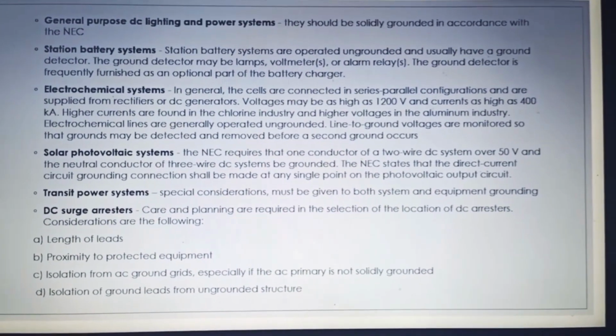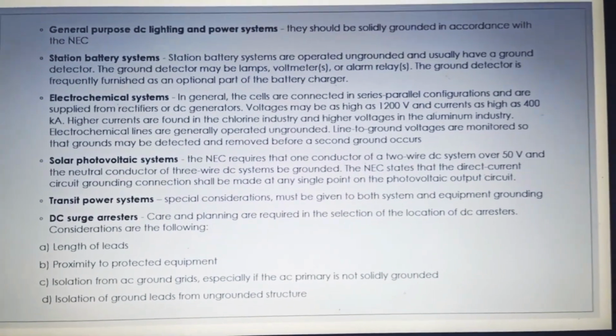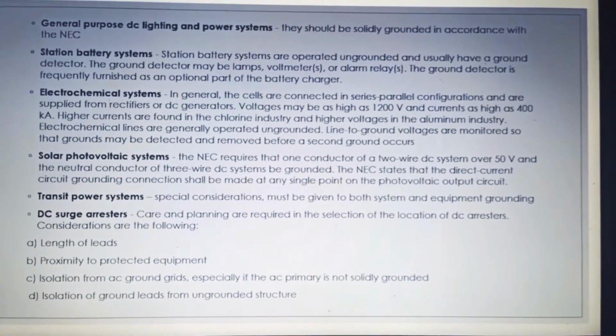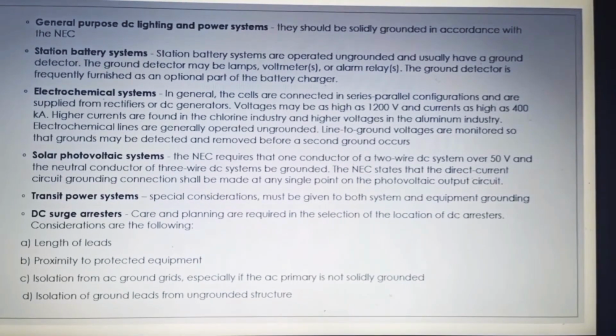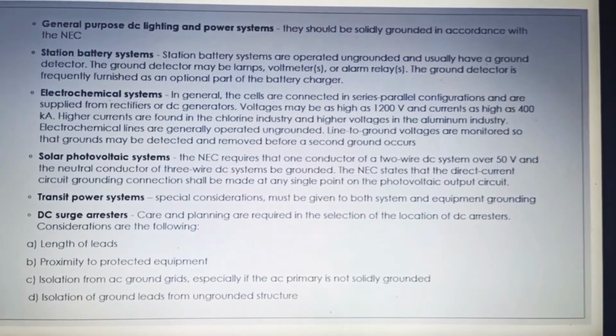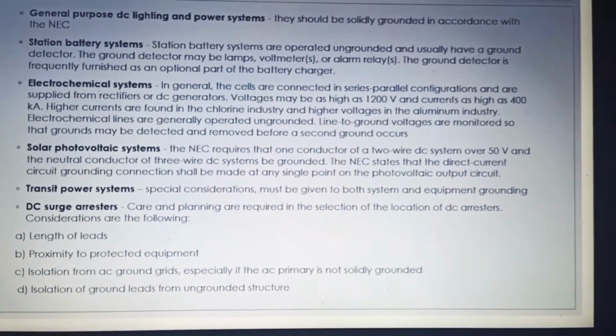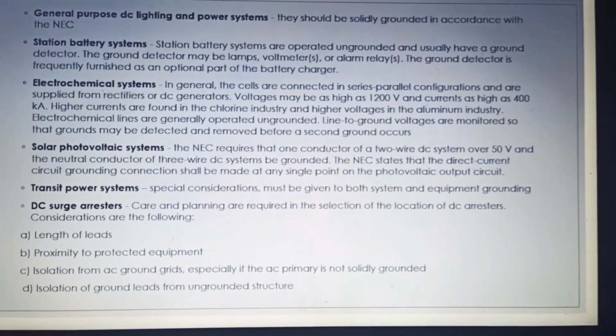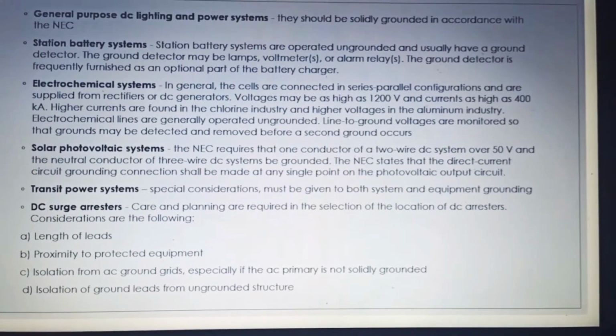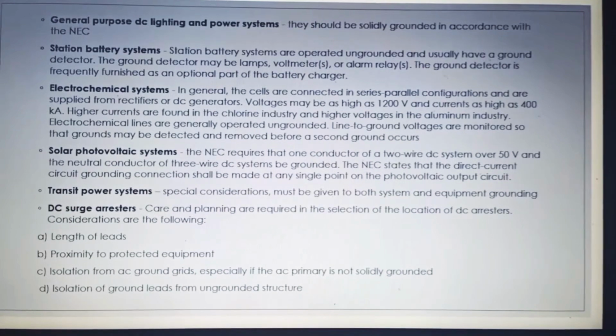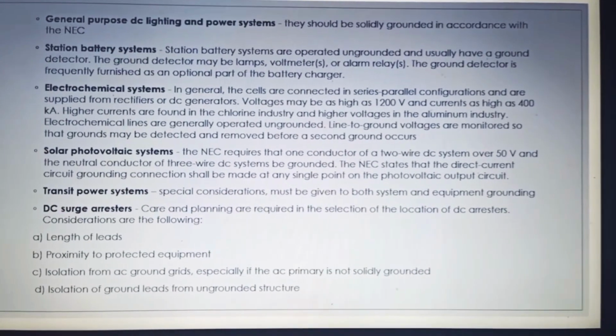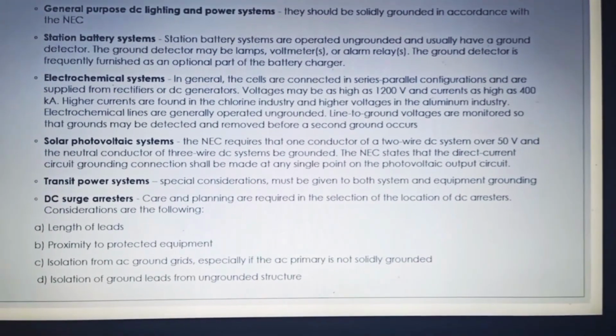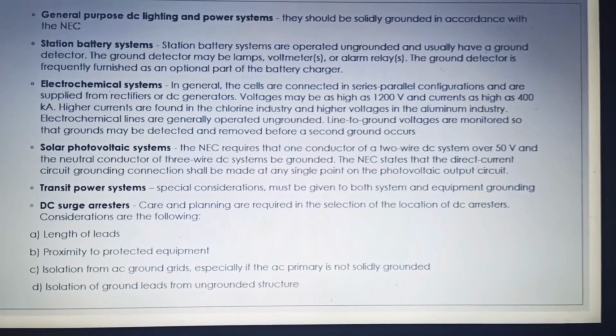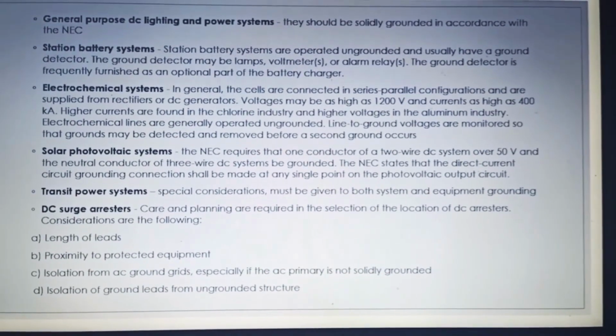In general, the cells are connected in a series-parallel configuration and are supplied from a rectifier or DC generator. Voltage may be as high as 1200 volts and the current as high as 400 kiloamperes. Higher currents are found in the chlorine industry and higher voltages are found in the aluminium industry. Electrochemical lines are generally operated ungrounded.